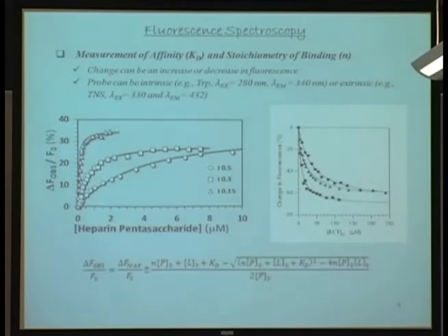And in essence, depending on how stable the instrument is and depending on the signal counts per second that you get, you can complete this experiment. Theoretically, you should complete it in less than half an hour. It also depends on the stability of the protein. Antithrombin is reasonably stable, though it does tend to aggregate. But for the most part, you can do an experiment such as this in approximately half an hour. So you should be able to do multiple experiments in a day.